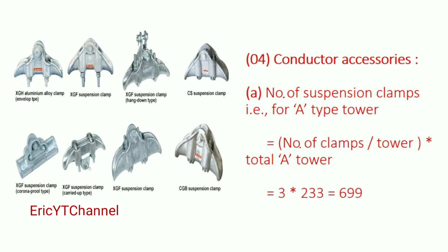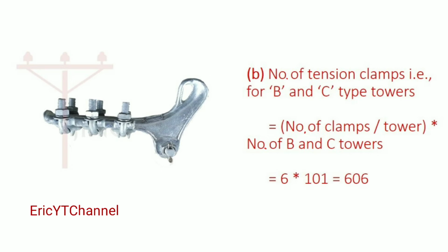Number 4 is conductor accessories. Letter A. Number of suspension clamps, that is for A-type towers, equals number of clamps per tower times total A towers equals 3 times 233 equals 699. Letter B is number of tension clamps, that is for B and C type towers, equals number of clamps per tower times number of B and C towers equals 6 times 101 equals 606.